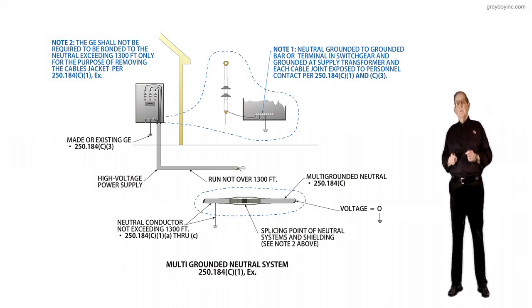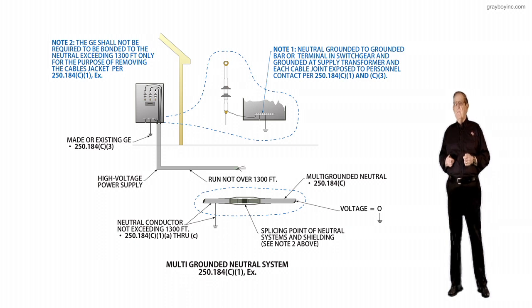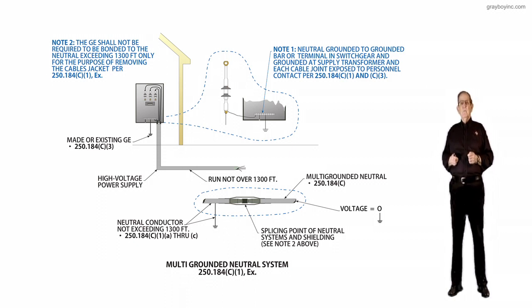This illustration deals with multiple grounded neutral type systems in accordance with 250.184(C)(1) exception. Purpose of change: a new exception was added and accepted. This new exception was added to clarify that the National Electrical Safety Code, NESC, recently revised their language to allow long cable runs such as those for wind farms and solar farms to still be considered a multiple point grounded type system, but not held to the 1,300-foot maximum length between bonding of the neutral conductor to a grounding electrode.